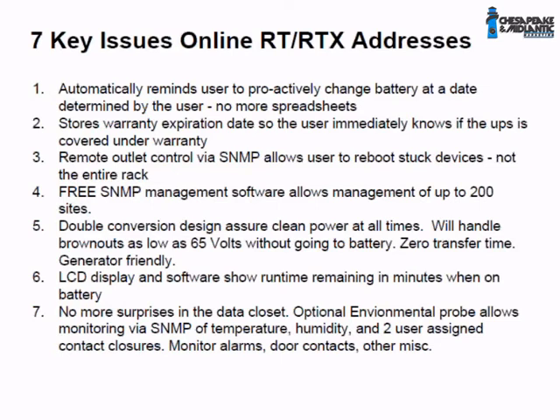To go through the 7 main issues: first, it automatically sends a battery change reminder. When the unit is set up, the customer can say, 'I want you to remind me 3 years from today to change the batteries.' It lets the customer determine the battery change interval, whether that's 3, 3.5, or 4 years. A lot of IT managers keep an enormous spreadsheet listing all their UPSs, tracking install dates and maintenance, which is a big headache. With these systems, they can basically throw out the spreadsheet.